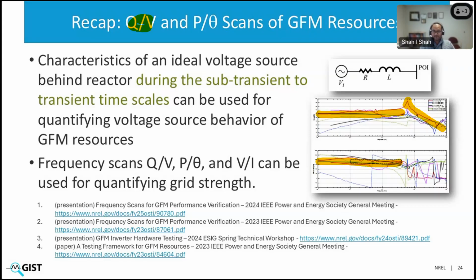Now, if the voltage is stiffer, for example, if this inductance is small and that grid forming resource is providing more voltage stiffness, that means these P by theta and Q by V scans will have higher gain. It will basically go up, and you can use that gain to quantify the grid strengthening behavior from grid forming resources. We can use the Q by V and P by theta scans. We can also use impedance frequency scans for quantifying the grid strength. I won't go into the details about how to do this, but here are a few links to presentations where there are more case studies about how to do this.